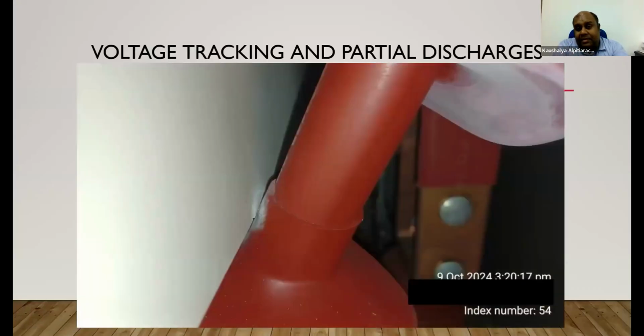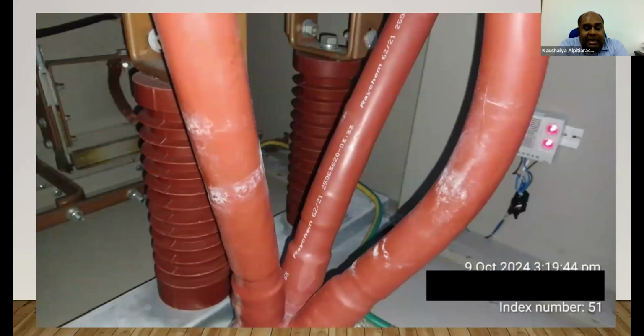Voltage tracking. Incorrect or unorthodox installations, leading the system to generate voltage tracking. You clearly see the barrier phase separator is touching your end termination kit and decreasing the clearance as well as creepage, which ultimately developed into partial discharges. You can see voltage tracking also at the shed, the upper shed at the bottom area. This again is a scenario that has voltage tracking.